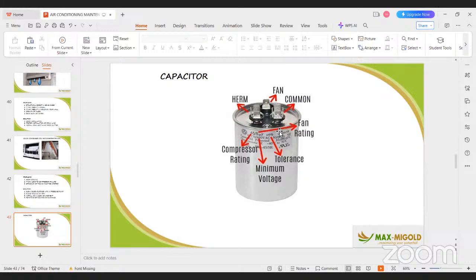Please take note: a real technician on site, once they remove your capacitor, will discharge the current by using two irons. You must wear a glove when you do it. Once you touch it, you will see a spark come out. Do it two or three times until the energy is discharged, but don't touch it directly with your bare hands.